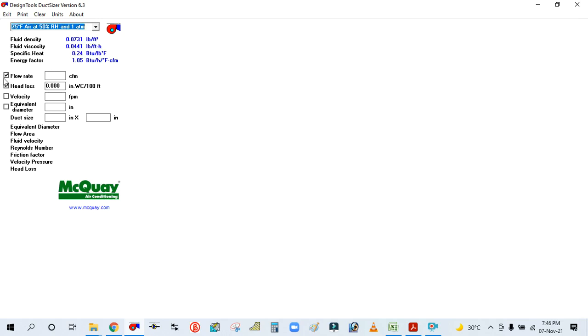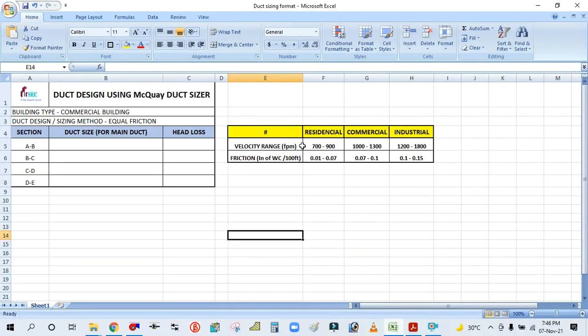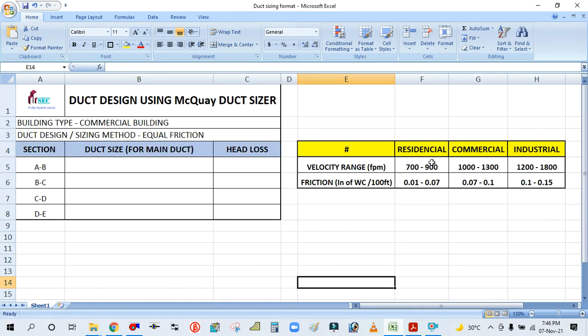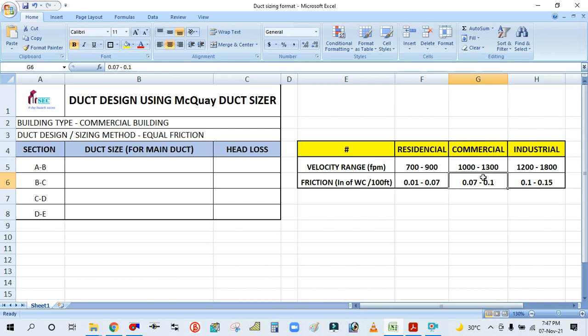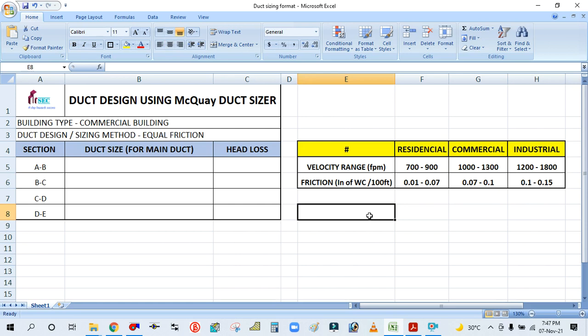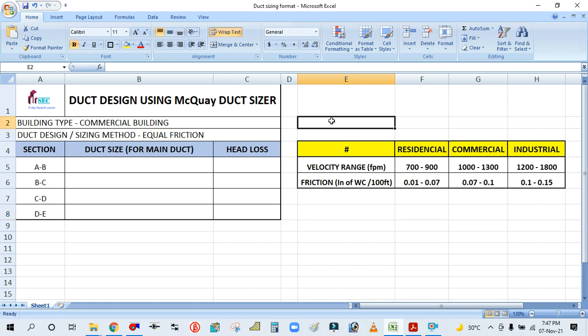For the equal friction method, simply select these two parameters: flow rate and head loss. Head loss is constant — in actual practice we consider 0.08 inches of water gauge per 100 feet. You can see the velocity ranges: for residential 700–900 feet per minute, for commercial 1000–1300 feet per minute, and for industrial 1200–1800 feet per minute. Friction loss ranges are: residential 0.01–0.07, commercial 0.07–0.1, and industrial 0.1–0.15 inches of water per 100 feet.